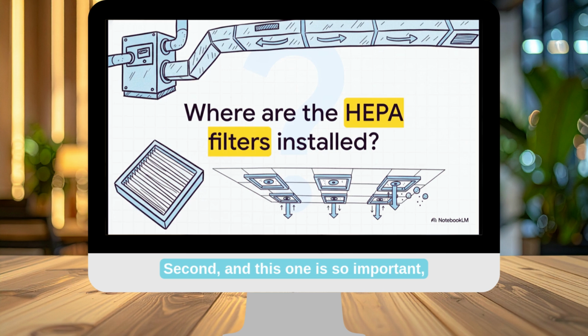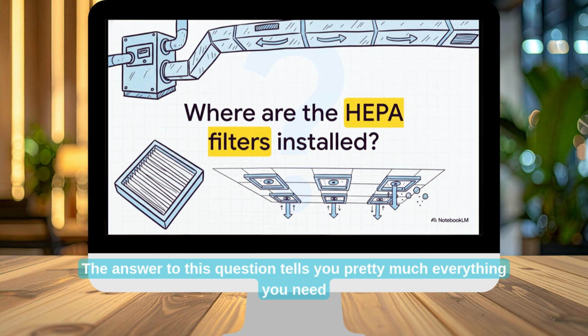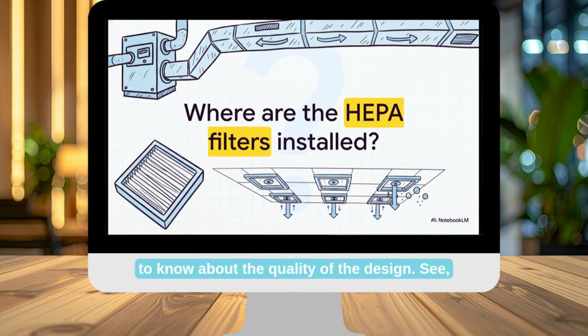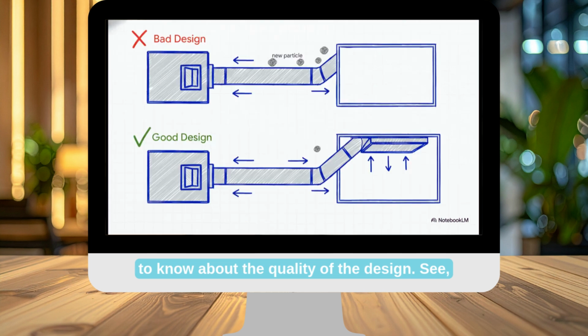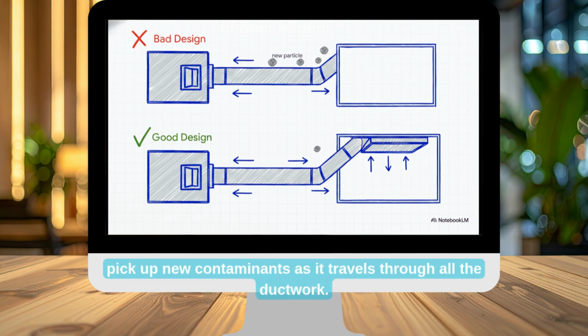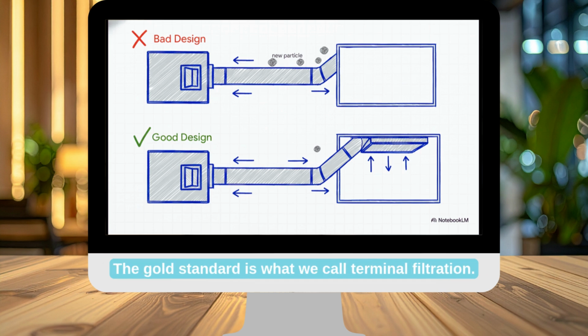Second, and this one is so important, ask where the HEPA filters are physically located. The answer to this question tells you pretty much everything you need to know about the quality of the design. A poor design will stick the HEPA filter way back inside the AHU. The problem with that is that the now clean air can pick up new contaminants as it travels through all the ductwork. The gold standard is what we call terminal filtration, where the filter is the very last thing the air passes through, right there in the ceiling of the clean room itself. This guarantees the air entering that critical space is absolutely as pure as it can be.